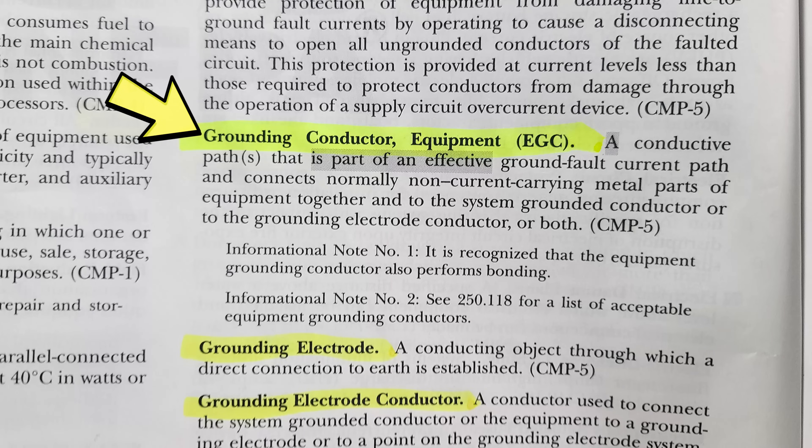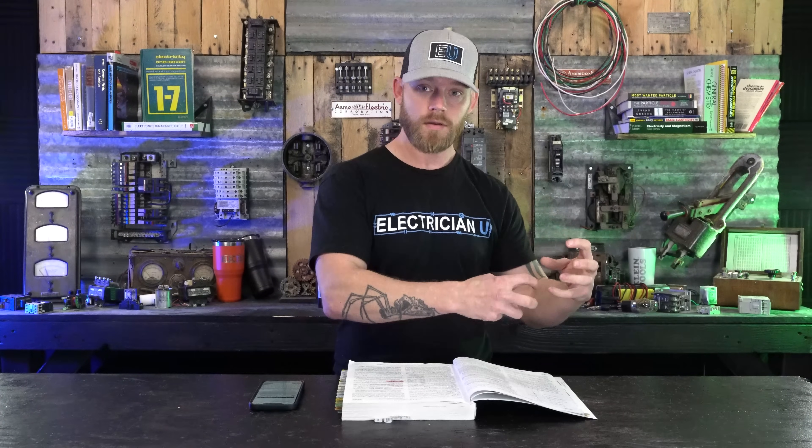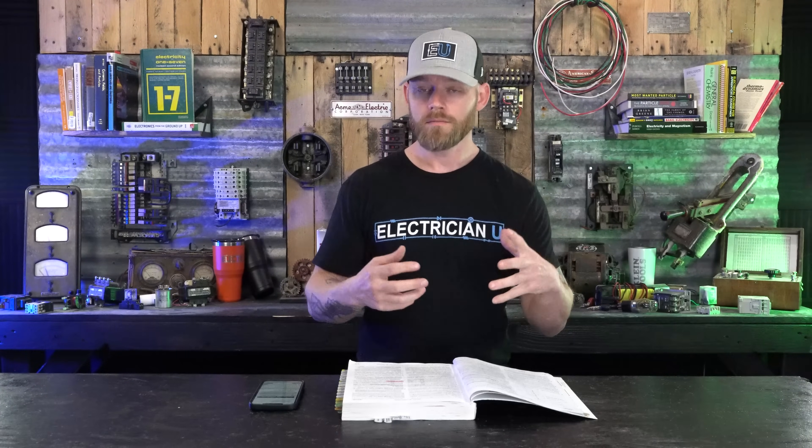An equipment grounding conductor — what we call the ground — is a conductive path or paths that is part of an effective ground fault current path and connects normally non-current-carrying metal parts of equipment together and to the system grounded conductor, or to the grounding electrode conductor, or both. So the equipment grounding conductor carries fault current back to the grounded conductor or the grounding electrode conductor — the one that goes down to the ground rod — or potentially both of them. So there is a difference between them.